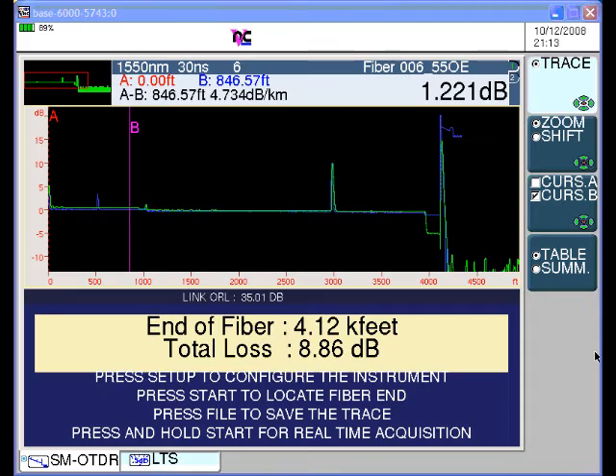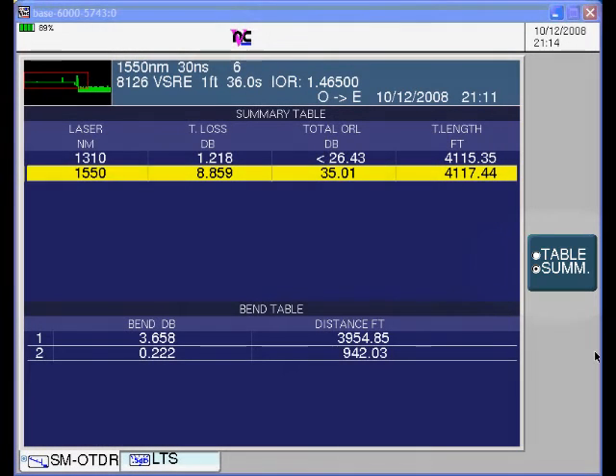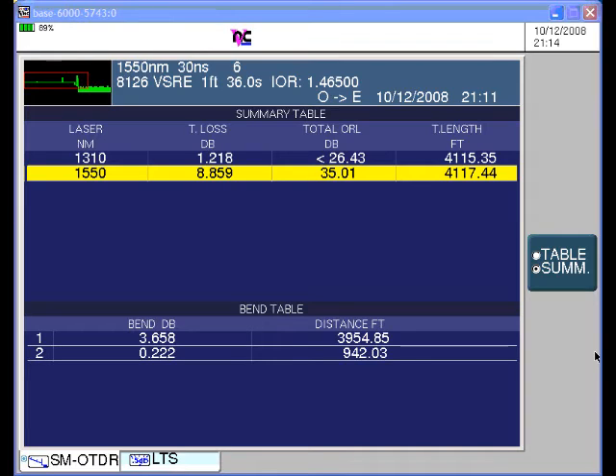This large loss event would typically indicate a bending problem. We can press the fourth function key, the table summary key, to go to the summary screen. On the summary screen, the total loss, total optical return loss, and total length at 1310 and 1550 nanometers is displayed. Also below is the bend table showing the worst three bends located in the fiber by comparing differential loss at the two wavelengths, with the most significant bending problem shown first — not necessarily the nearest bend. We can see that there is a bend of about 3.6 dB difference between 1310 and 1550 nanometers, and the distance to this bend is about 3,900 feet.